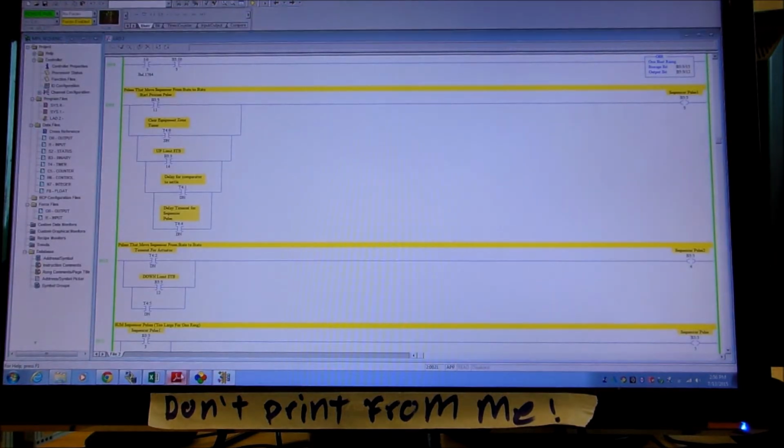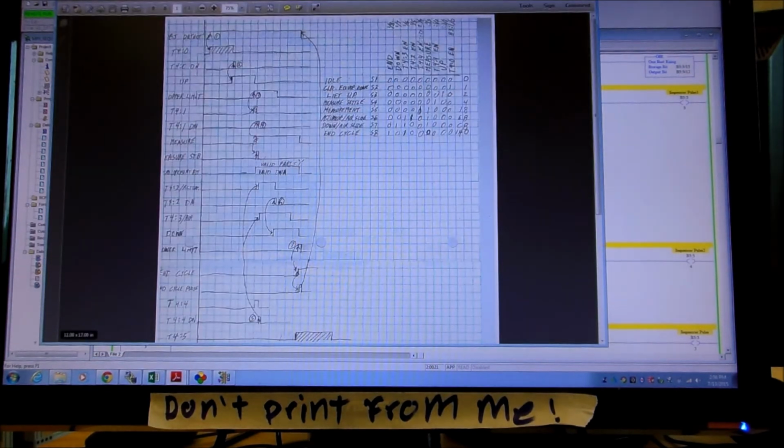And so what we do is we have this final timing diagram where we have these states and we detect something, and then that sets off a timer. Timer's done, we get the done bit, that sets off the up bit, and so on. And we keep rumbling through in sequence through the state machine. Now over here is the states that we have. This is state 1, state 2, and what we do in each state. And here's the values that we're actually putting in the sequencer. It's an output sequencer, so these are the values that are getting shifted into the output sequencer.